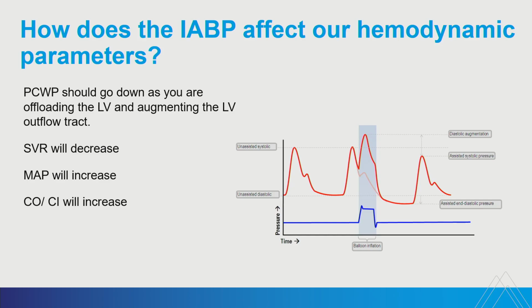A balloon pump will not run unless it has a trigger. So if there's no trigger, it goes on standby. It is safely deflated, but it's not helping the patient. It's not harming the patient. However, you never want the balloon to be on standby for greater than 30 continuous minutes, as blood may collect in the folds of that catheter. And on our machine, it will give you a blue banner how many minutes you've been in standby.